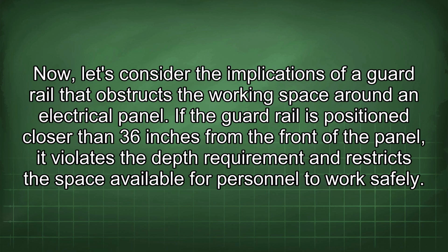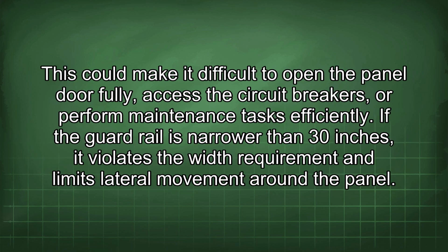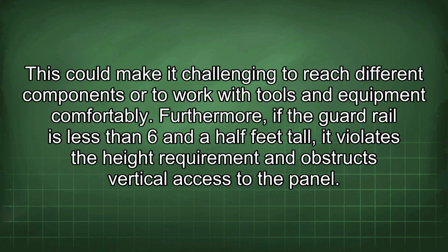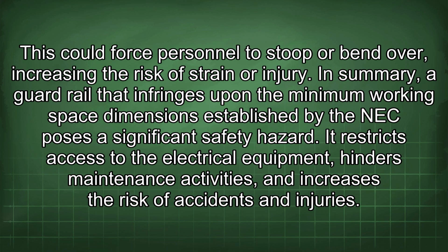Now, let's consider the implications of a guardrail that obstructs the working space around an electrical panel. If the guardrail is positioned closer than 36 inches from the front of the panel, it violates the depth requirement and restricts the space available for personnel to work safely. This could make it difficult to open the panel door fully, access the circuit breakers, or perform maintenance tasks efficiently. If the guardrail is narrower than 30 inches, it violates the width requirement and limits lateral movement around the panel. This could make it challenging to reach different components or to work with tools and equipment comfortably. Furthermore, if the guardrail is less than 6.5 feet tall, it violates the height requirement and obstructs vertical access to the panel. This could force personnel to stoop or bend over, increasing the risk of strain or injury.